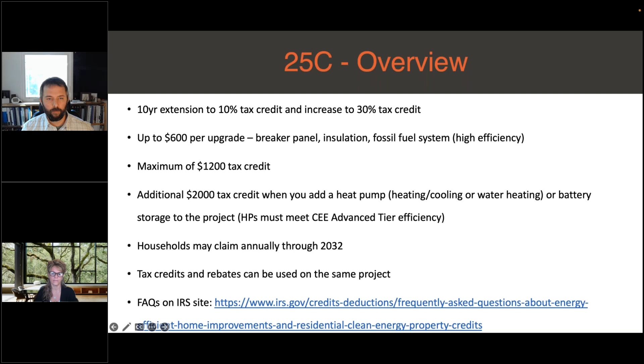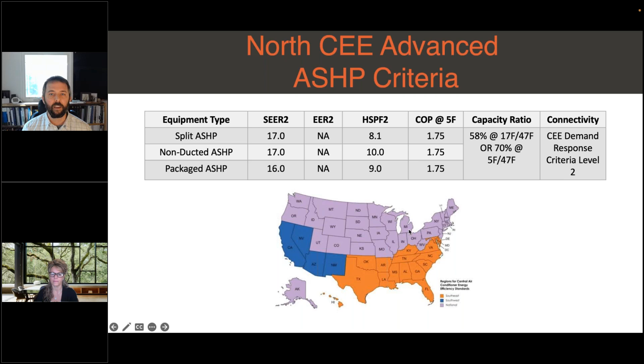So to qualify, air source heat pumps under 25C must comply with the Consortium for Energy Efficiency's advanced tier criteria. For the purple section, these are the requirements for SEER2—there's no requirement for EER2—HSPF2, and then some low ambient heating requirements as well. For the south, the orange section, we get rid of those low ambient heating requirements, but we add in the EER2 requirements, which is actually slightly tough for some manufacturers to meet for air source heat pumps.